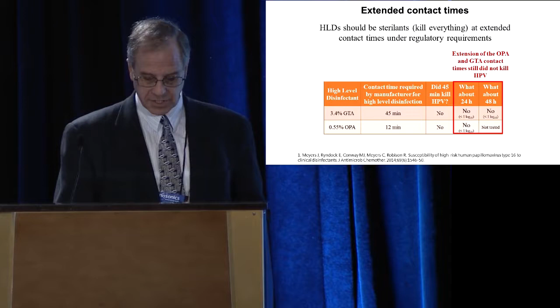So these challenges escalate the risk of HPV transmission with ultrasound probes. HPV is found on probes and probe sheaths after use. HPV remains on the probe after cleaning. High-level disinfectants, GTA and OPA, are HPV ineffective. They do nothing against HPV. HPV remains infectious for several days. The probe is reused. HPV transmission occurs with skin and mucous membrane contact.